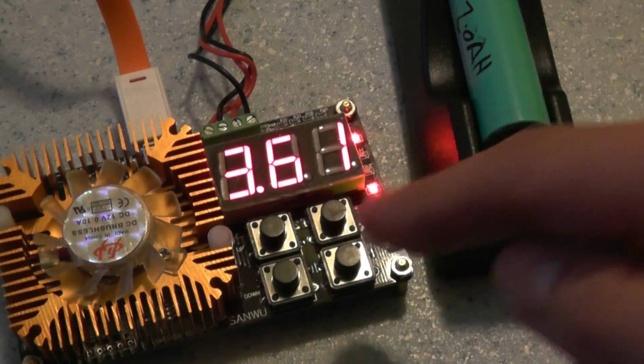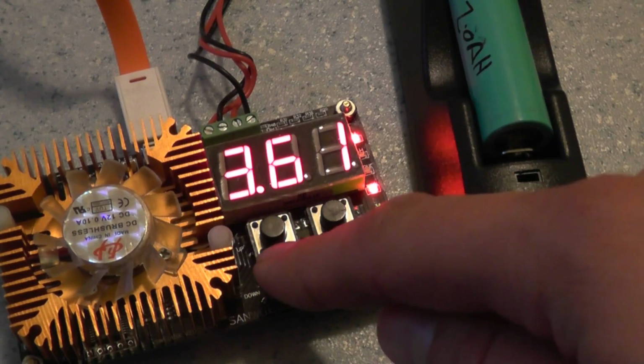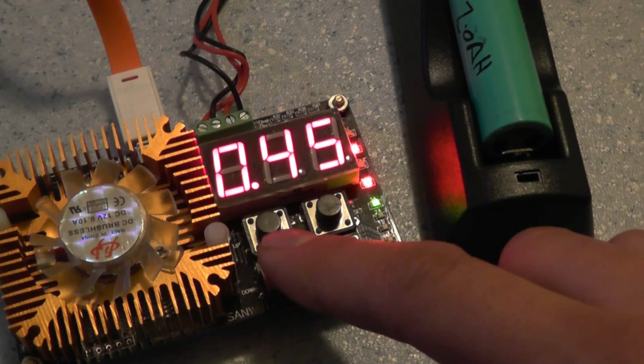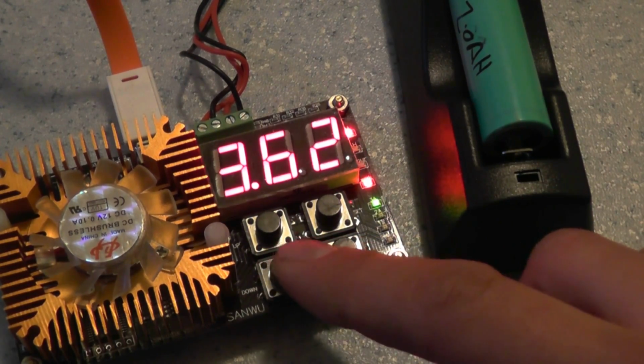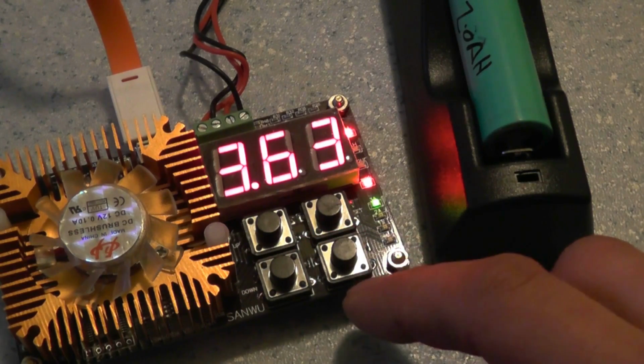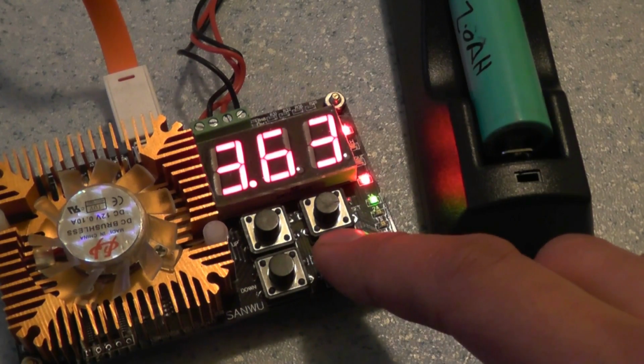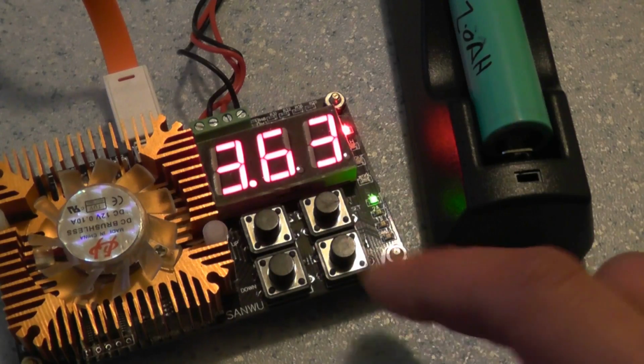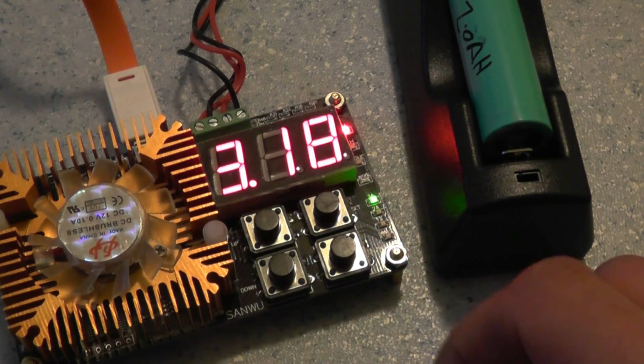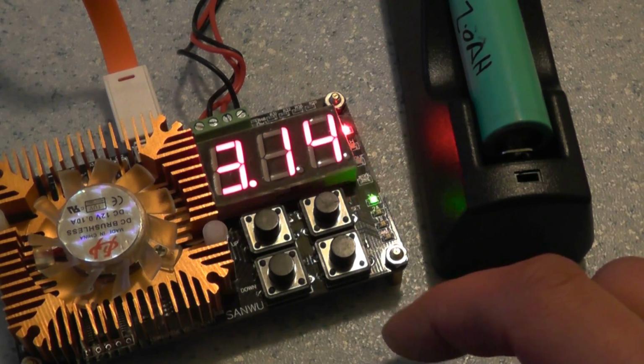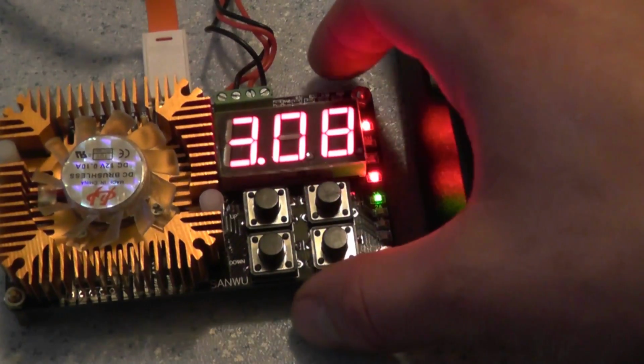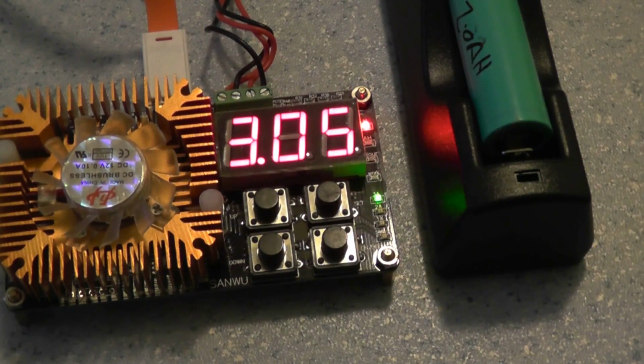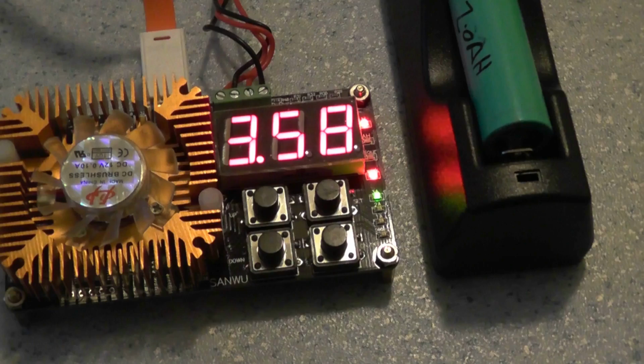Right, so we missed the end, but I can replicate the end quite easily. You can scroll through once the battery has finished its cycle and see it was on for almost 10 minutes. We took 450 milliamps out of it, and the voltage it stands at is 3.62. So by pressing start again, there we go, flashing, voltage drops. When it hits 3 volts, the discharge cycle stops, and then you get a series of bleeps, and the work light goes solid rather than flashing.